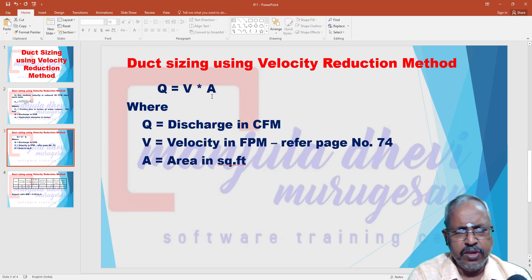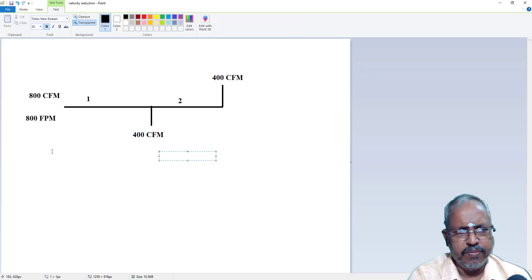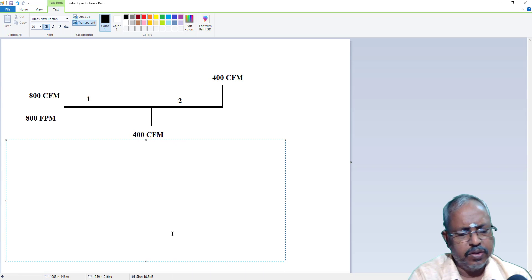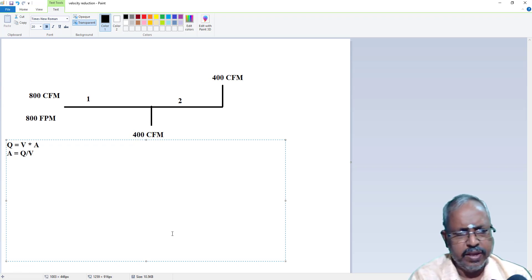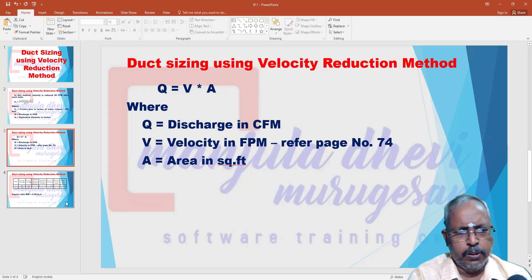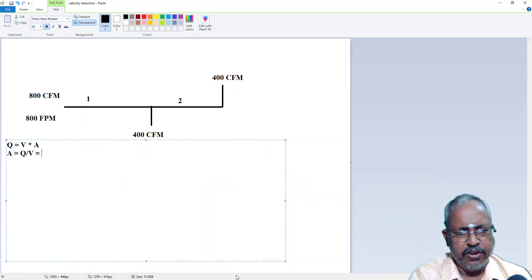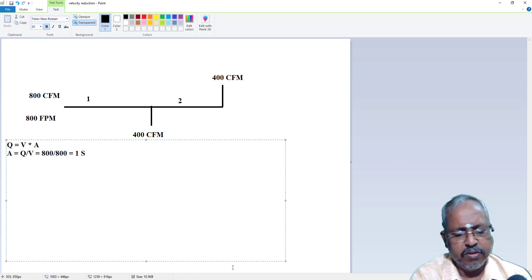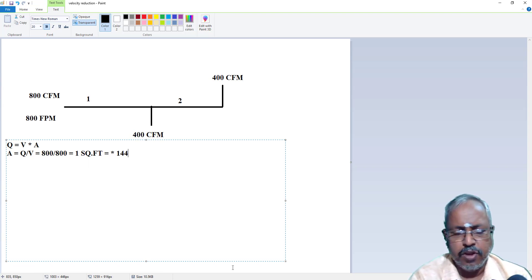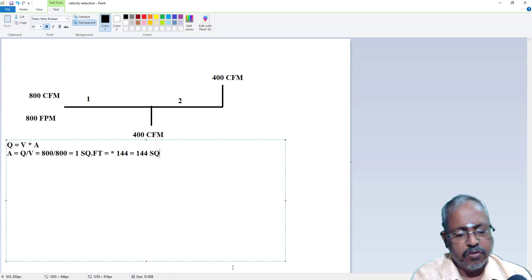We use Q = V × A, so A = Q / V. Q has a value of 800 CFM and velocity is 800 FPM. Therefore, 800 divided by 800 equals 1 square foot, which equals 1 × 144 = 144 square inches.